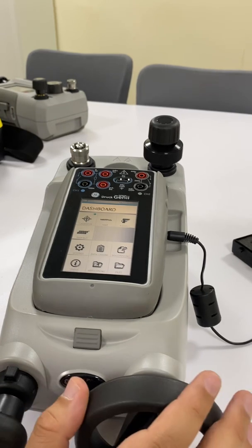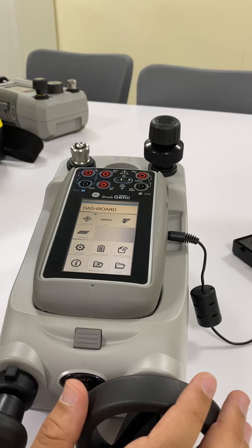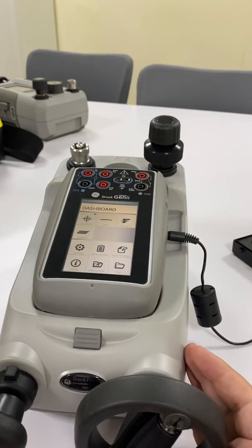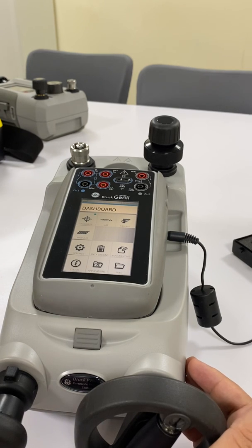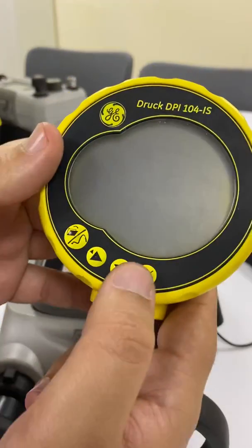So we will now do the high pressure calibration using the DPI 620 Genii and the PV622 pneumatic pressure station, which can do from vacuum to 100 bar. Let's do 70 bar today. We will be using the DPI 104 as the device under test.